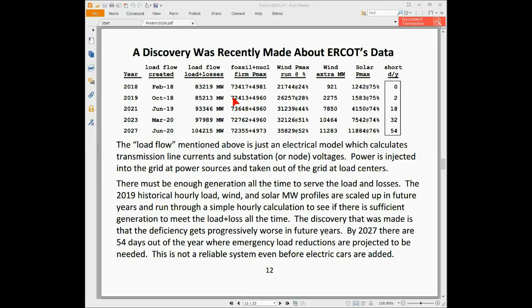This number, by the way, also includes the north and east DC type powers coming into ERCOT. Notice the wind has increased here. There's more installed wind in this case, and there's more installed solar. However, ERCOT had to increase the non-coastal wind above the 14.2% just to solve the load flow—they had to increase that wind by 2,275 megawatts above what it should have been running.